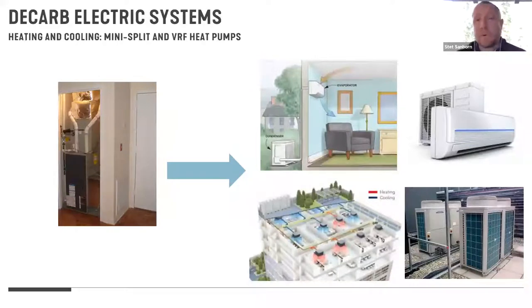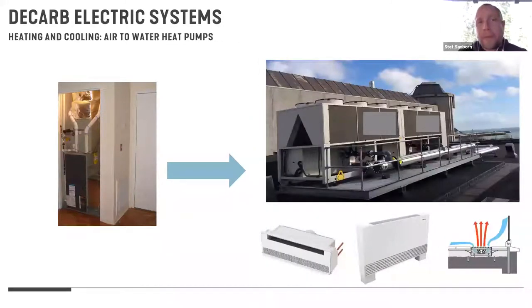So in general, what we're seeing in the marketplace is a pretty big move in system types. For instance, in multifamily residential, we're seeing a move away from traditional four pipe systems or in-unit furnaces, moving towards mini splits or VRF type systems in our climate zone. So all electric for heating and cooling, combining one appliance that can do both. For projects at scale, we have a number of projects that are using air-to-water heat pump systems. So there are four pipe systems. Usually the ones that we like to use involve heat recovery. So true four pipe systems that can do simultaneous heating and cooling or bias whichever load is the greatest and then still provide heat recovery. Those systems for us, with our utility rates, provide phenomenal performance for our clients.